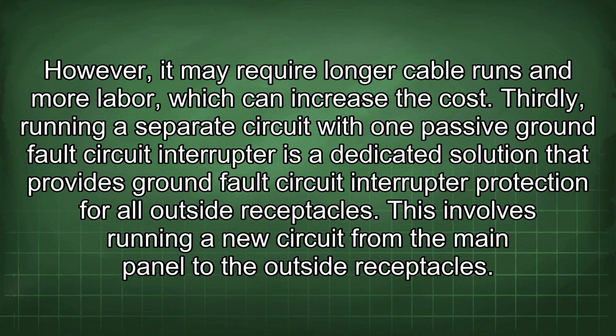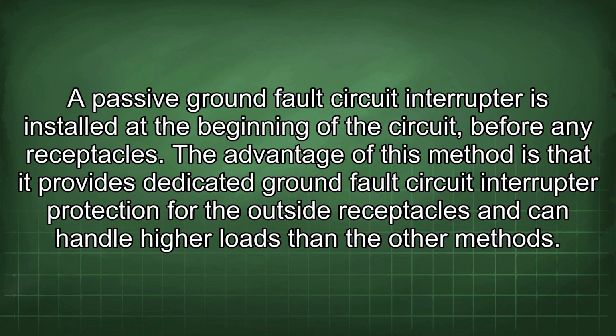Thirdly, running a separate circuit with one passive ground fault circuit interrupter is a dedicated solution that provides ground fault circuit interrupter protection for all outside receptacles. This involves running a new circuit from the main panel to the outside receptacles. A passive ground fault circuit interrupter is installed at the beginning of the circuit before any receptacles. The advantage of this method is that it provides dedicated ground fault circuit interrupter protection for the outside receptacles and can handle higher loads than the other methods.